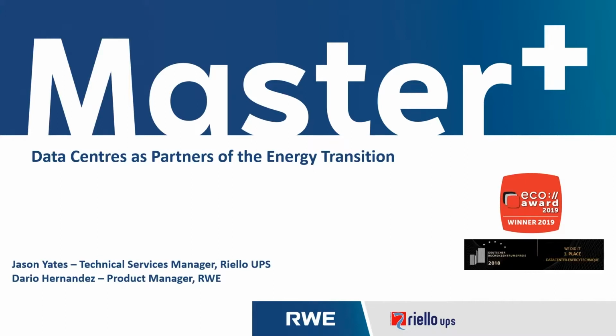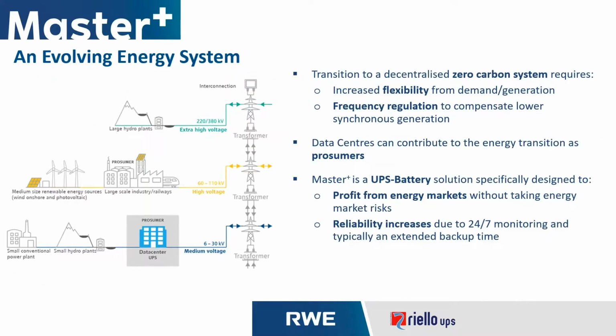Now, the Master Plus is effectively a UPS system which has been specifically developed in order to enable data centers to become partners of the energy transition. As the electrical systems around the world continue to evolve, with greater demands being placed upon the need for renewable energy, in addition to the implementation of smart grid-ready technology, the primary goal is to make the transition to a decentralized zero-carbon system. Obviously, this requires significant increases in flexibility from the demand and generation perspective, whilst at the same time providing frequency regulation in order to compensate for lower synchronous generation.